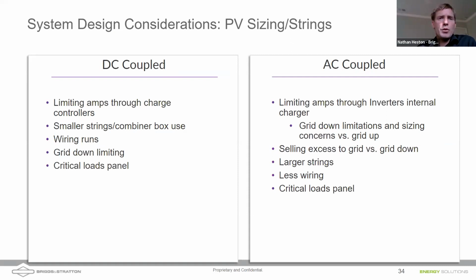So it's important, as you're considering the size of your strings as well, not to exceed the power limitations of your equipment. That, of course, makes sense, but there are also some considerations as to when the grid goes down, how your battery is coupled to your system, and making sure that you don't exceed the power capability of your battery to take power in from that AC coupled grid.